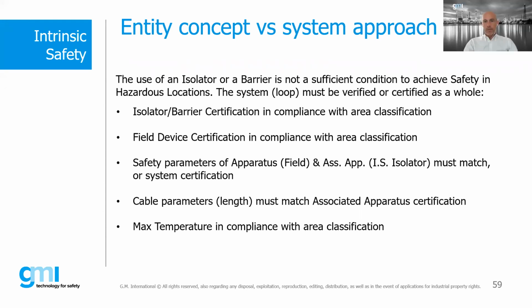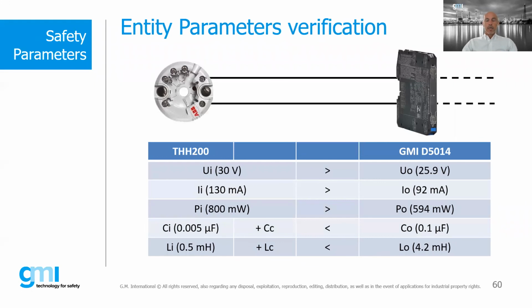Maybe you already know that if you have a cable that has specific parameters, those parameters have a big influence if you stretch this cable over a longer distance, a very long distance. And also the max temperature must be compliant with the classification. Here there is an example, where you have the field apparatus with Ui, Ii, Pi, Ci, Li for the field device, and the barriers have certain Uo, Io, Po, Co, Lo.